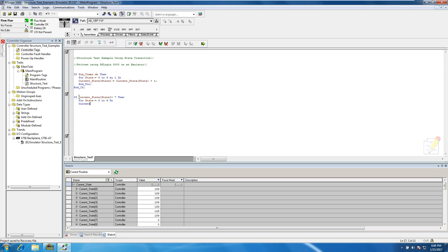Inside the FOR loop body we write: current_state - our array again - with indirect tag addressing equals 0. This is basically clearing all the properties. Then we END_FOR and END_IF. I like to keep everything capitalized correctly - I put the wrong indicator there, but the software will tell you that. We all have typos.